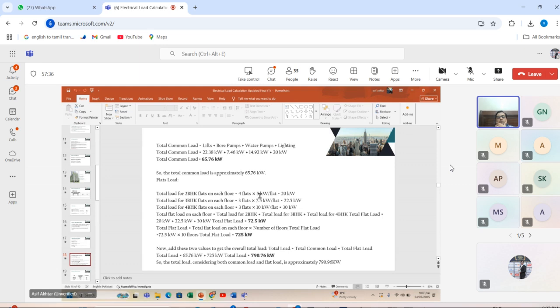Third is the total load for 4 BHK flats, which is 3 flats. So in each floor there are 10 flats: 4 flats of 5 kilowatt, 3 flats of 7.5 kilowatt, and 3 flats of 10 kilowatts. So now the total flat load on each floor is the total load for 2 BHK plus the total load for 3 BHK plus the total load for 4 BHK flats, which is equal to 20 kilowatt plus this. Now the total floor load is 72.5 kilowatt. So this is the calculation of all the loads of 2 BHK, 3 BHK, and 4 BHK apartments.